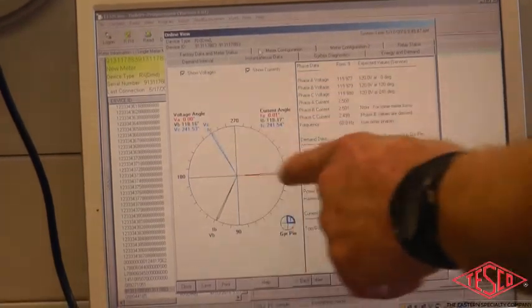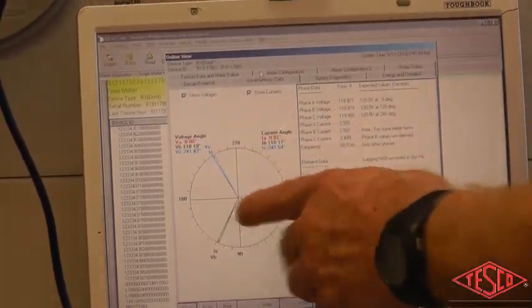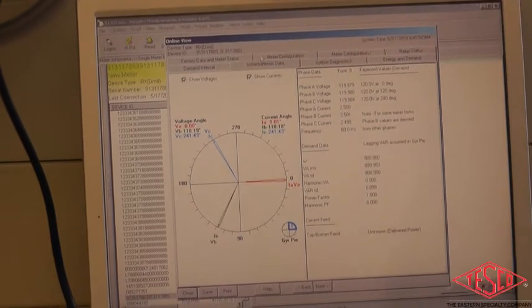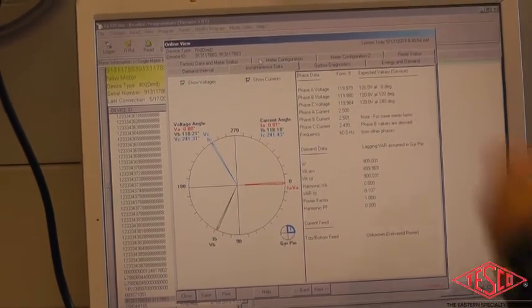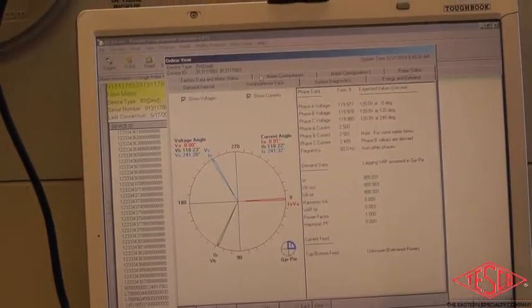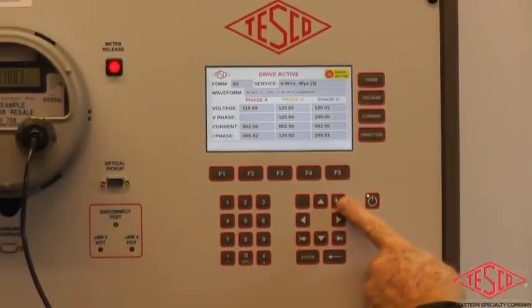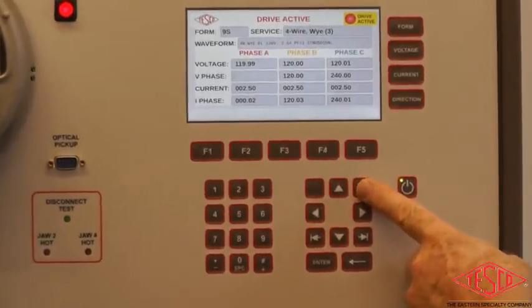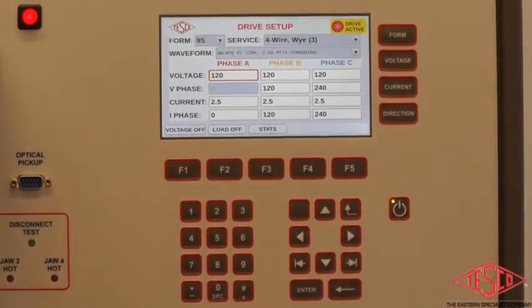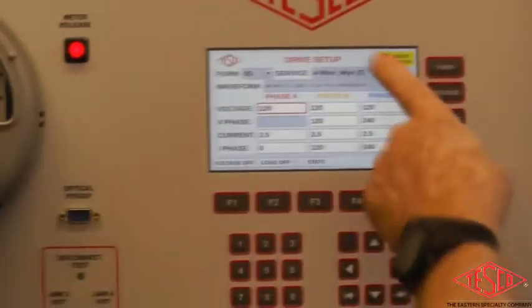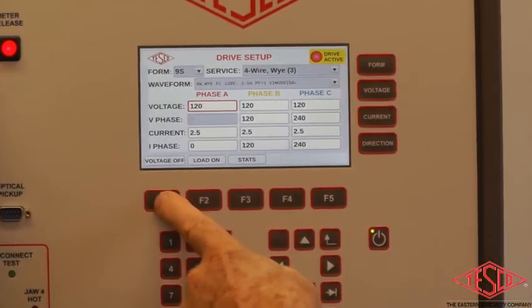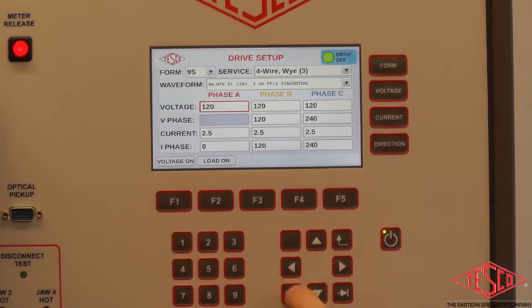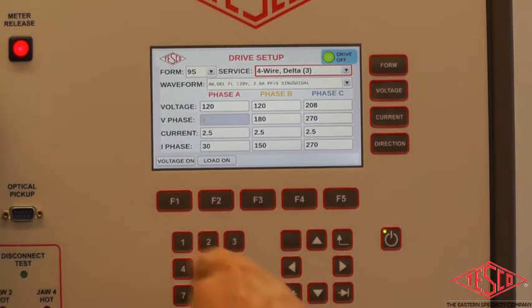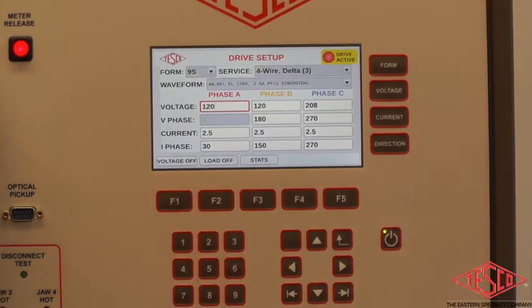So here you can see the voltage and the current of the meter, and it's in a Y configuration, so the voltages and currents are in line, 120 degrees out of phase with each other. So the way to go to the next higher screen is always this arrow key. This backs out to the next screen. So now if I want to change the supply to a delta, I can turn load off and voltage off and change the 4-wire Y to a delta, and energize the voltage, energize the current.